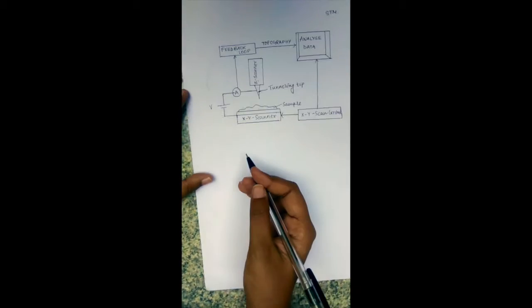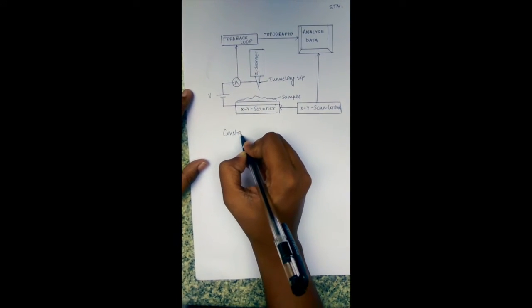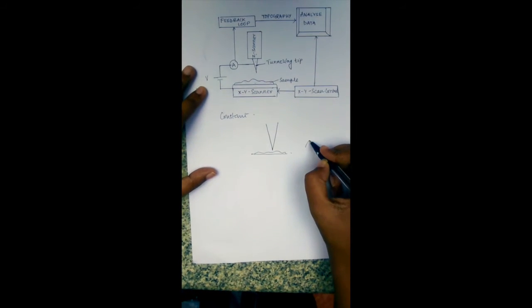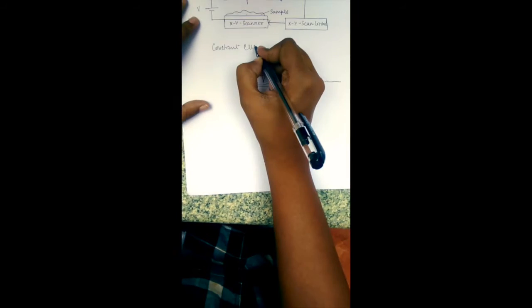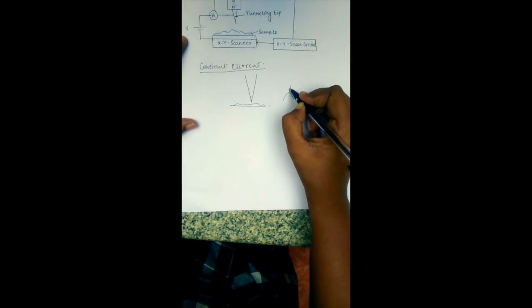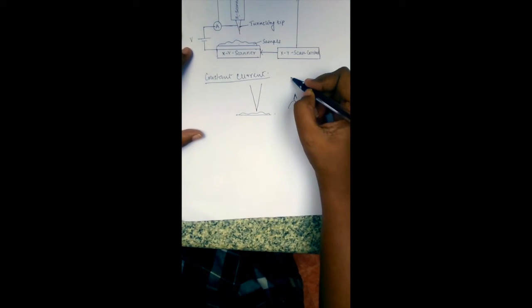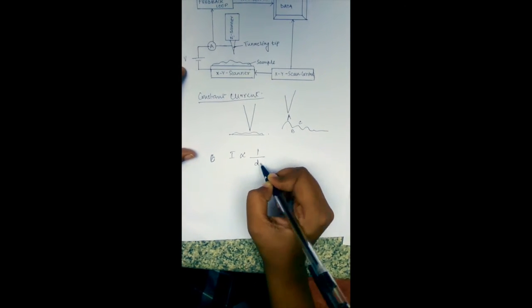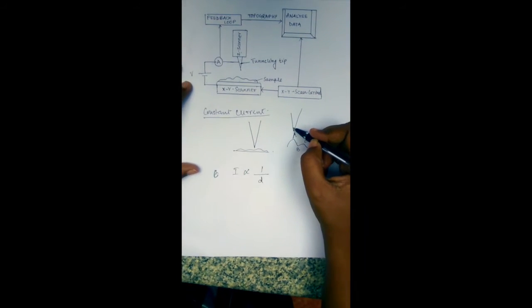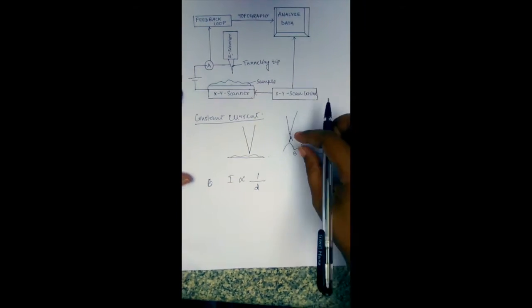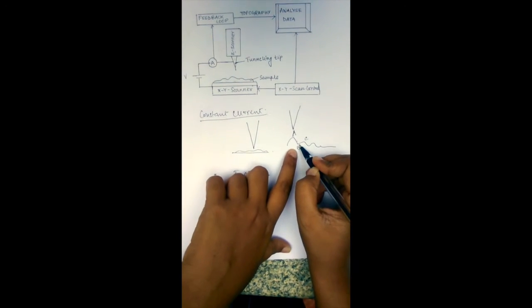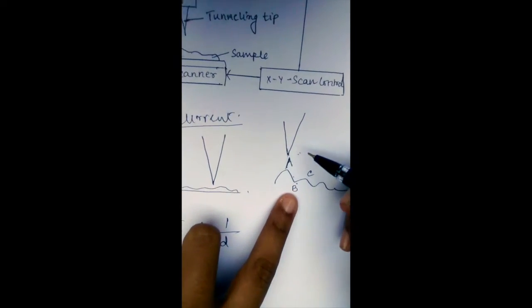There are two modes of a scanning tunneling microscope: constant current and constant height. In the constant current mode, suppose the surface has irregularities at points A, B, and C. The current generated is inversely proportional to the distance between the tunneling tip and the surface. When the tip is closer to the surface at point A, a strong current is generated. As the tip shifts toward region B where the distance increases, the current decreases.